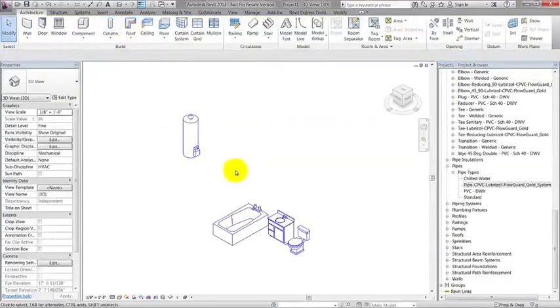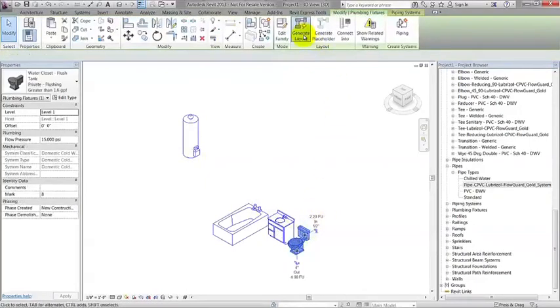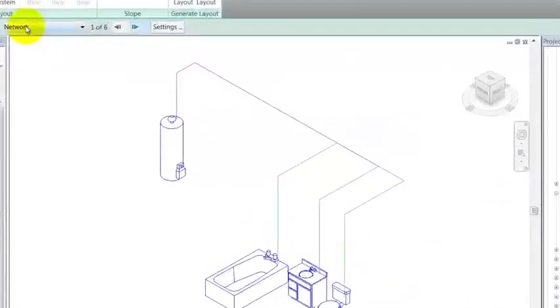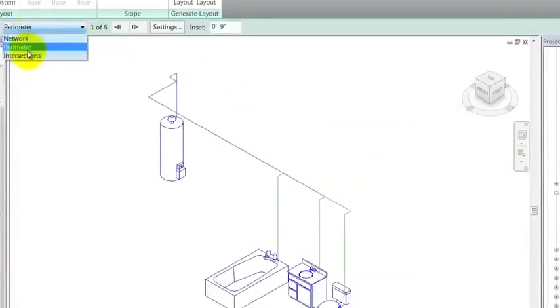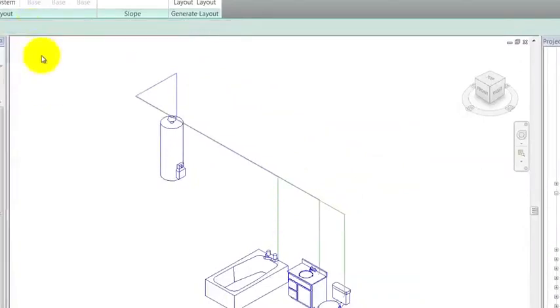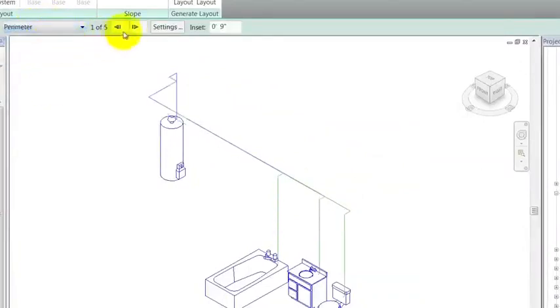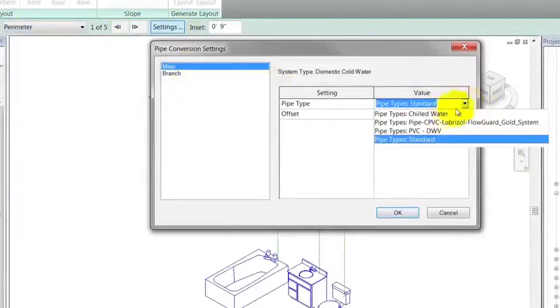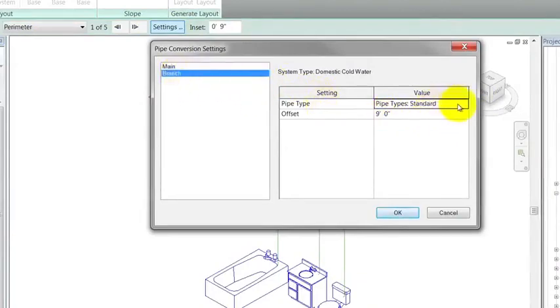I will now generate a piping layout by selecting the water closet and clicking on the Generate Layout tool. This will give us different solutions. Select one. Now we need to make sure this layout will use the FlowGuard Gold Pipe, so click on the Settings button to select that pipe. Must select the FlowGuard Gold Pipe in both Main and Branch, then click OK.